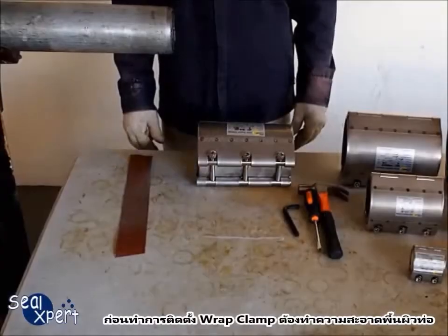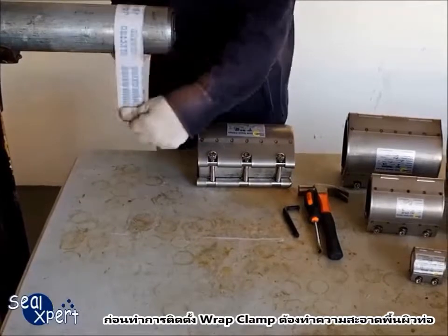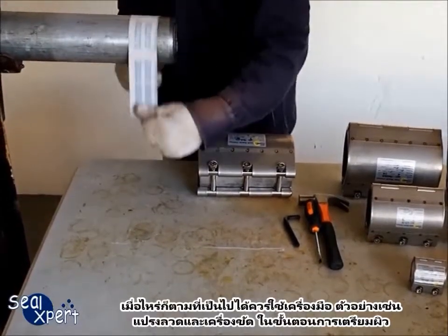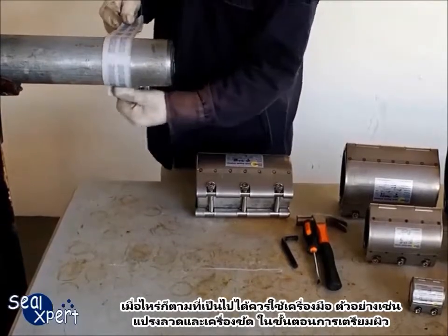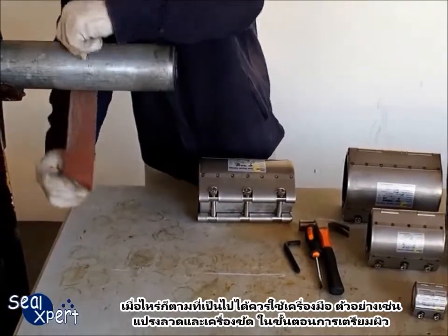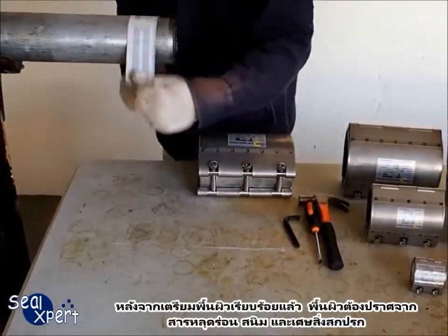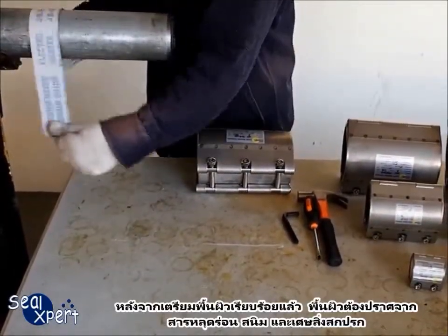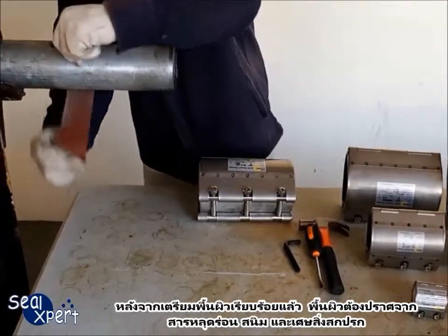Before installing the Wrap Clamp, you will need to clean the pipe surface. Whenever possible, you should use a mechanical power tool, for example, wire brush and grinder, to perform surface preparation works. After the surface preparation is completed, the surface should be free of loose particles and debris.